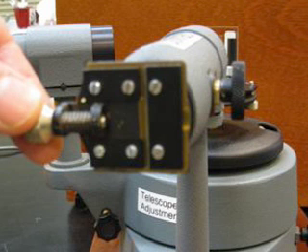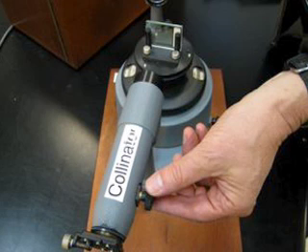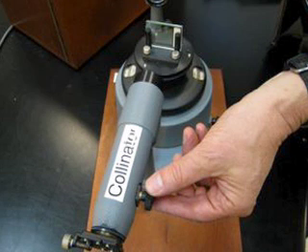Once you have adjusted the slit width, you will focus the beam using a knob similar to the one on your telescope. The position of the knob may vary by model. Turn the knob while looking through the telescope. If your telescope is positioned opposite the collimator, you should be able to see the slit as a bright line.